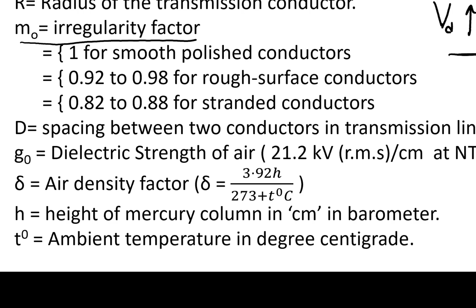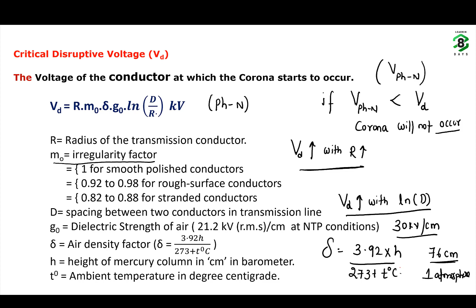Next, air density factor. So, air density factor takes care of the atmospheric pressure and the ambient temperature. Even the occurrence of corona depends upon the atmospheric pressure condition and the ambient temperature condition. So that is taken care of by this air density factor. So delta is given by what? Air density factor is given by 3.92 H divided by 273 plus T, where H is the height of mercury column in centimeter in barometer. So for 1 atmospheric pressure, how much will be the barometer height of the mercury column? 76 centimeter. That is equal to 1 atmosphere pressure. And T is the ambient temperature in degree centigrade. Okay. So basically, the corona occurrence depends upon the size of conductor, spacing between the conductors, shape of the conductor, and atmospheric pressure and temperature conditions. Okay.